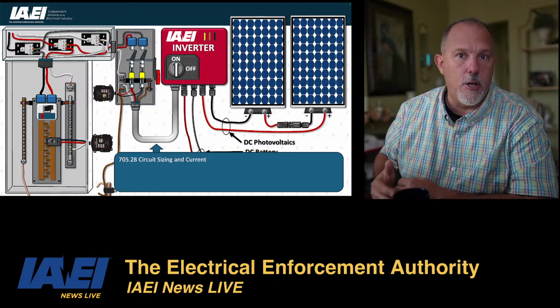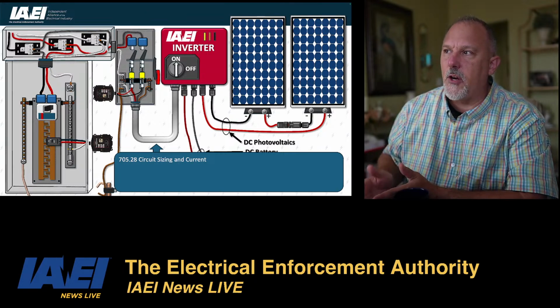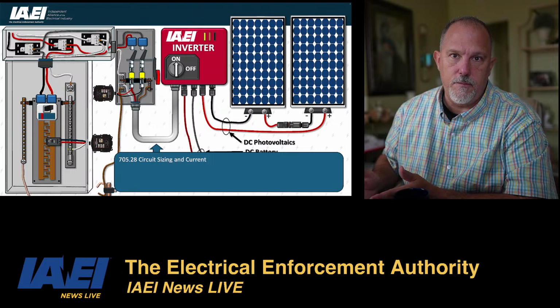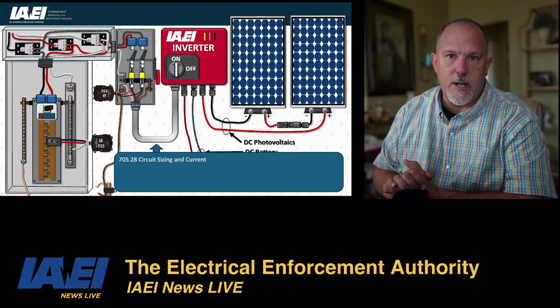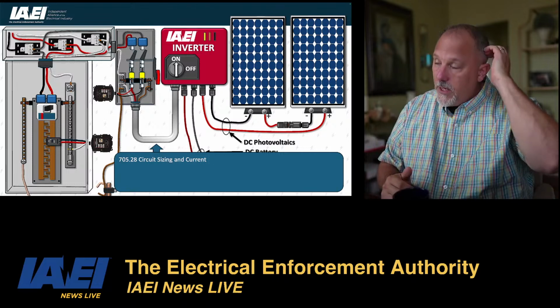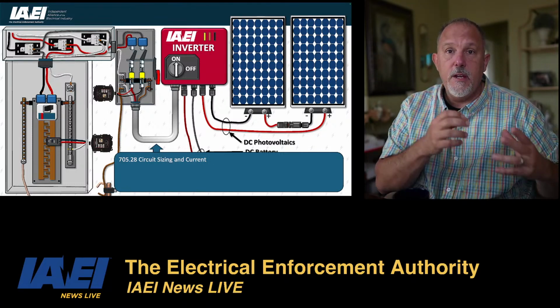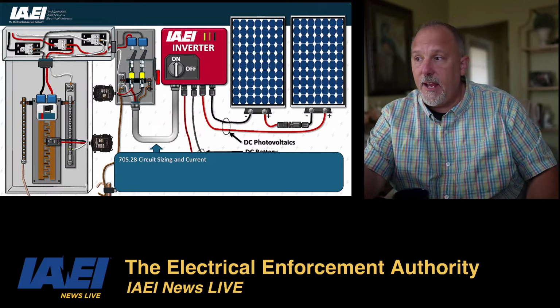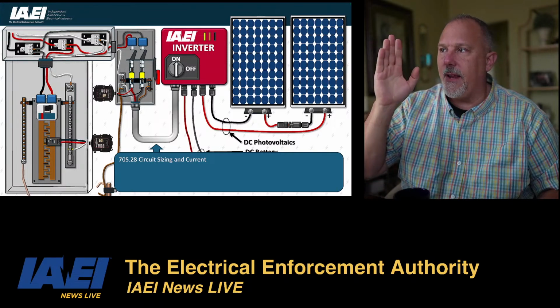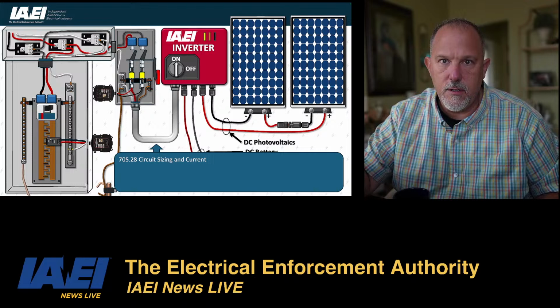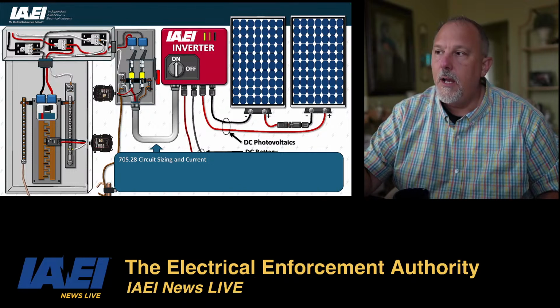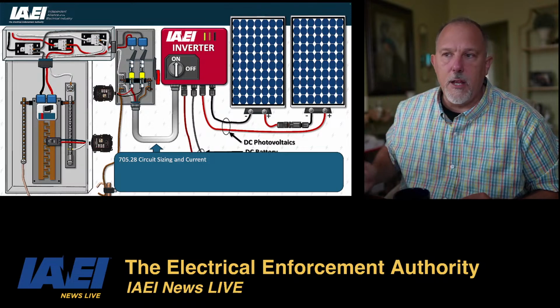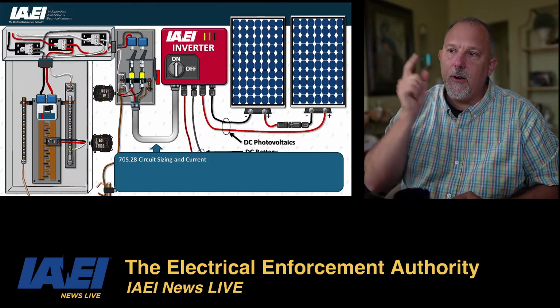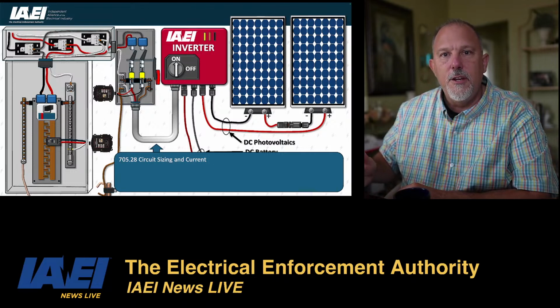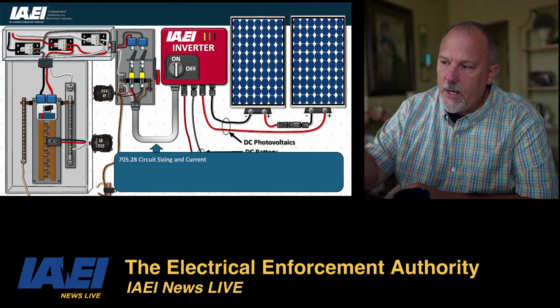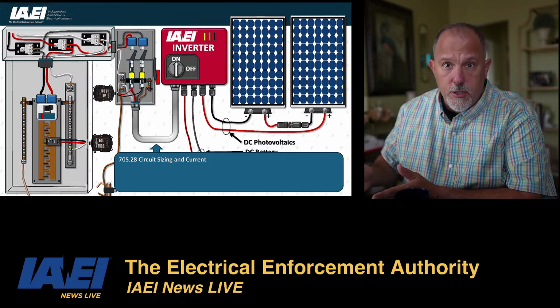I'm not calculating a load current. I'm calculating the amount of current that inverter can put out. That's how I'm going to size those conductors. So for that reason, we don't go back to Article 215 for sizing those conductors. And in the case of when my inverter was my service equipment, I don't go to Article 230 to calculate my loads on that conductor, because Article 230 is going to talk about load currents. We need to talk about source currents.